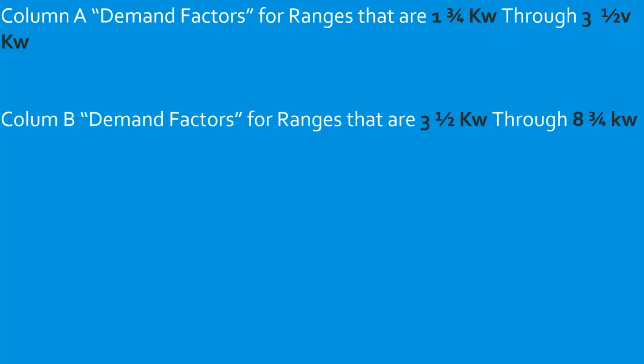Now let's look at column B. It is also a demand factor, and it's for ranges that fall in between 3.5 and 8 3/4. If we had one range that was 7 kW, we would come over to the left-hand side first and find our number of appliances. Then we would come over and tee off with the respective demand factor in column B. In this case, it's 0.80. So we'd take our 7,000 VAs, multiply it by 0.80, and that would be our new demand. Same thing if we had two appliances. Let's imagine that we had two 7 kW. We would go on the left-hand side and first find our number of appliances. Then we would come over to column B because our range is in between 3.5 and 8 3/4, and we would have a 65% demand factor. We take 7, multiply it by 2. That's going to give us 14 kW or 14,000 VAs. Then we would multiply that by 0.65, and that's going to give us our new demand that we actually calculate for our load calculation.